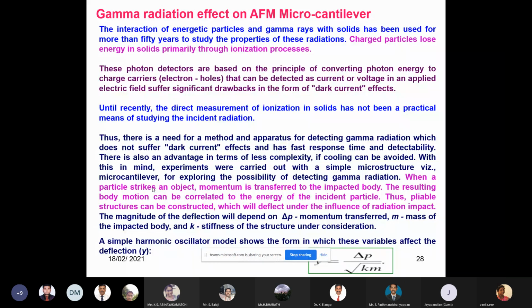Dark current means that because of temperature variation, without any radiation falling on it, the heating effect causes a noisy signal. For a low-level signal, gamma irradiation or alpha or beta particles falling, we are unable to measure quantitatively. Then we have to take care of the dark current, and the cost jumps up like anything. That time only we can think.